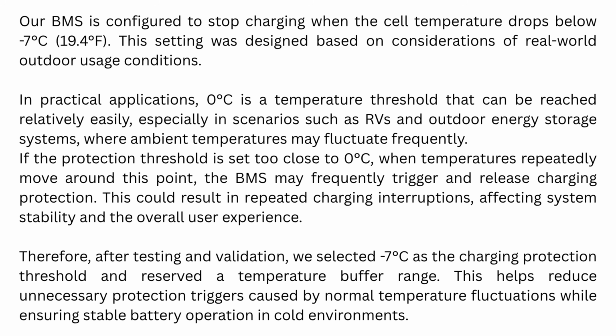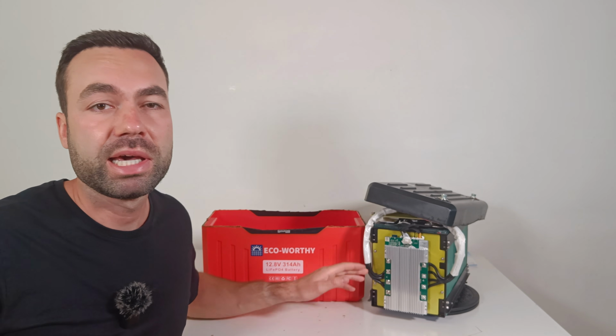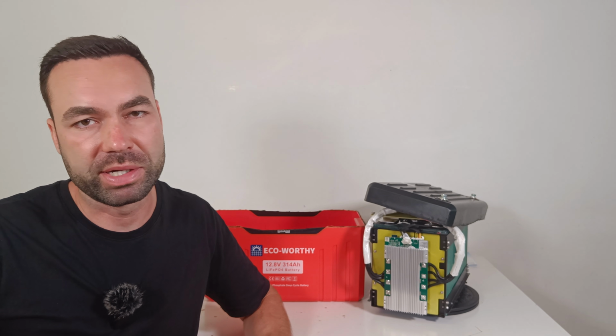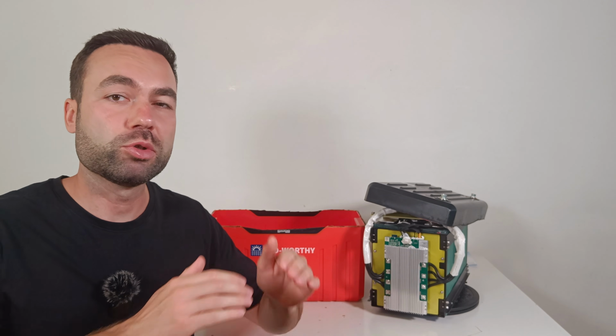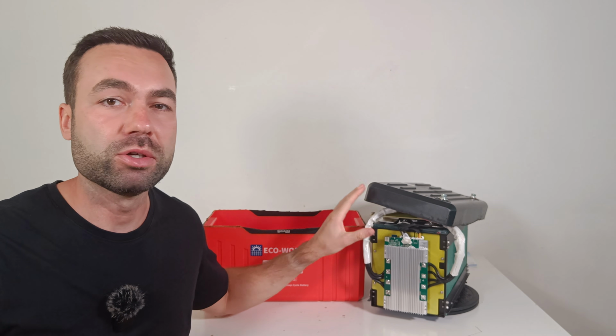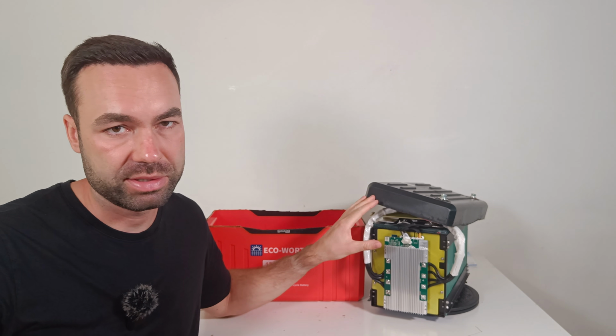And the second one is the low temperature cutoff. They say it's their way of reducing frequent tripping of the BMS during low temperatures, and after testing, they settled on -7 degrees Celsius or 19.4 degrees Fahrenheit. So what they are doing is building in more headroom for the battery to charge when it's frozen. And I don't agree with this practice.